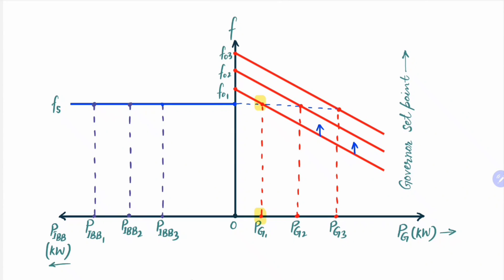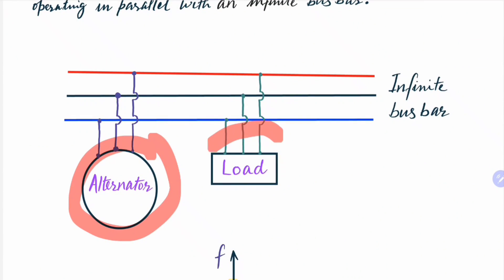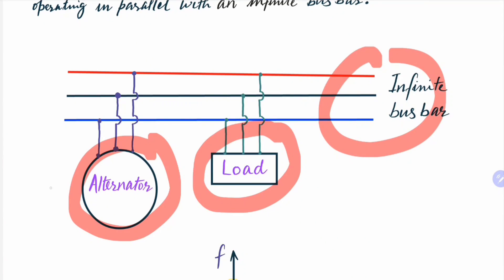Then its no-load frequency will shift up from f01 to f02. Once the mechanical input to the alternator is increased, that is once the governor set point is increased, this curve will shift up so that the no-load frequency of the alternator shifts up. Since the infinite bus bar frequency cannot be changed, it will be fixed at its normal value fs. The point of operation will shift so that the frequency remains fs and the active power supplied by the alternator will increase from a negligible value at synchronization to PG2.